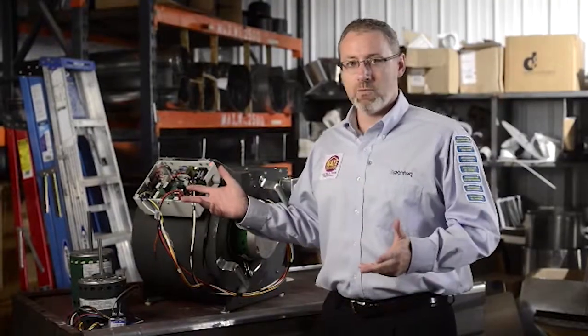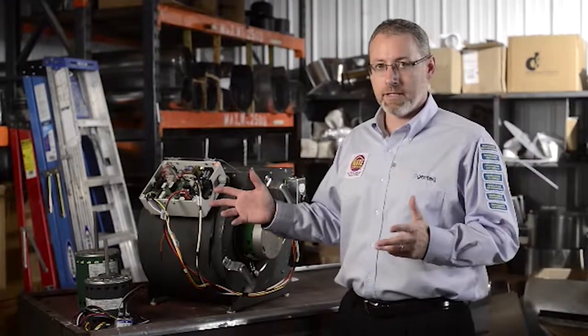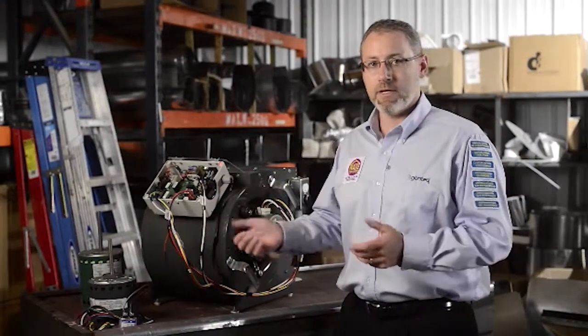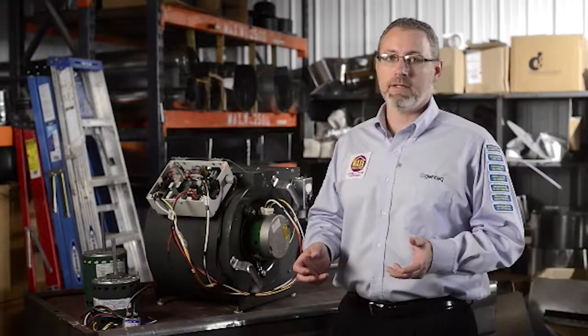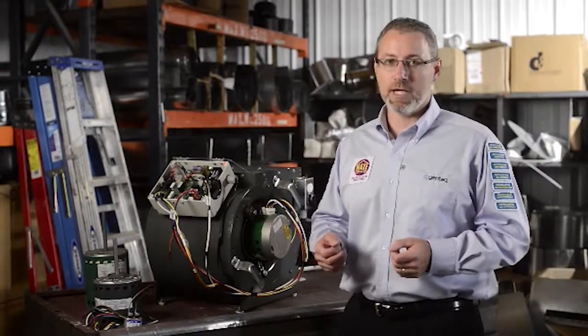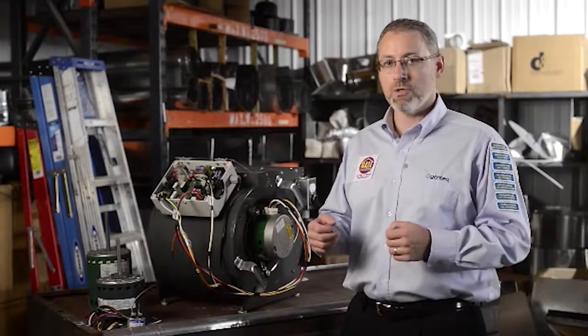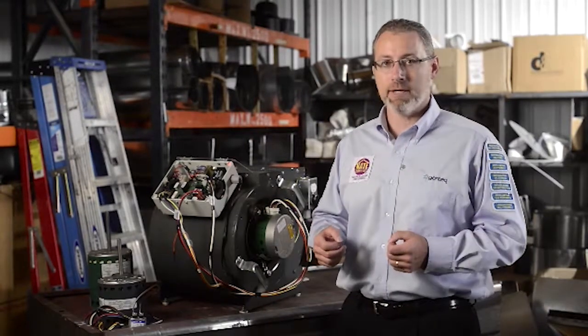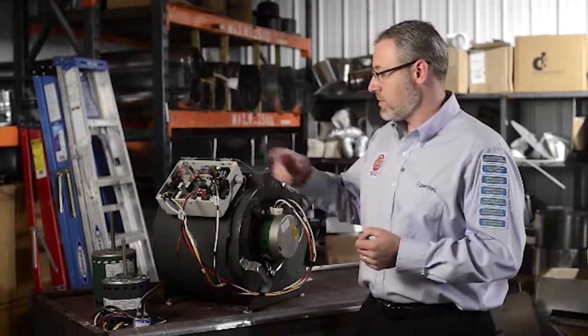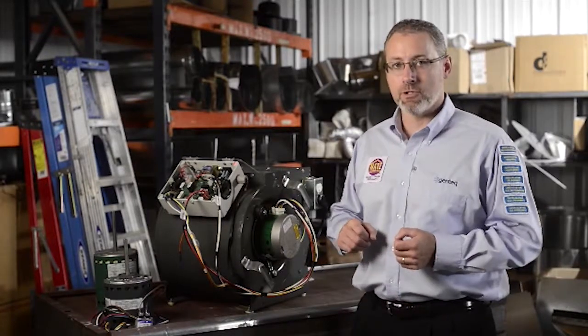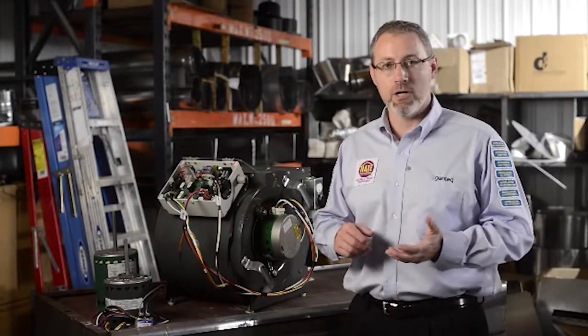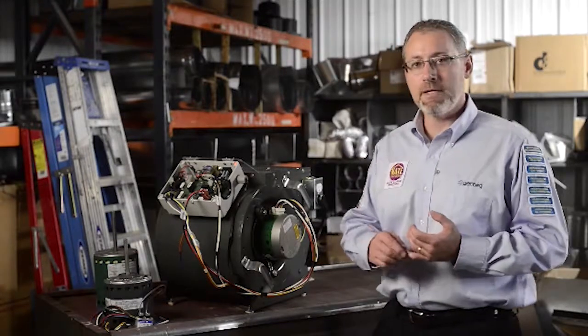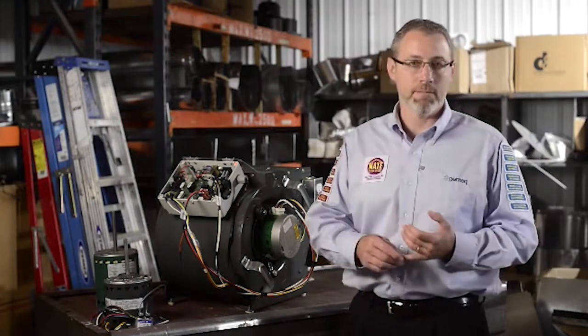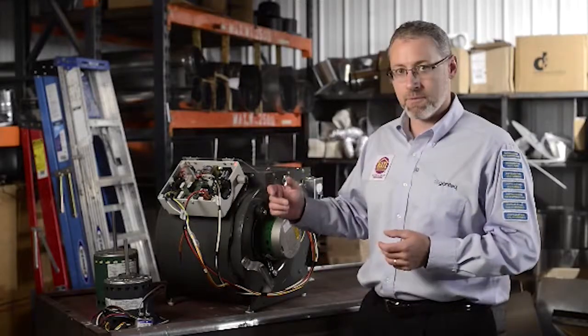So even though we've connected wires to this control board in a different configuration than the way the PSC motor was connected, we've still maintained the sequence of operation in the HVAC system due to the way that we've designed the Evergreen IM to operate. So when the thermostat sends a demand call down to the control board, it is going to turn on one of the speed taps. However, the speed taps are not an on command to the microprocessor.